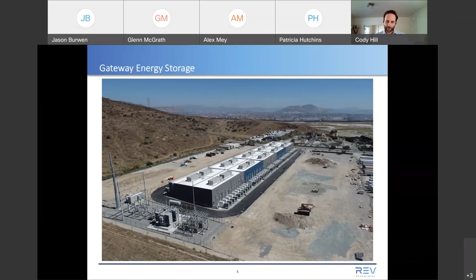These little gray boxes are the transformers that convert the 34.5 kV to low voltage for the inverters. The white boxes, each one is about a 3 megawatt inverter. It converts the AC to DC, and then the cables go inside to battery racks that look a lot like what you saw on the previous slide. Pretty much all of these battery storage facilities have that same architecture: 2 or 3 megawatt inverter stations is the most common, though you can also see smaller ones sometimes. It's really the same technology used on inverters from the PV space, so we've benefited from the scale of that much larger industry, being able to procure higher volume and lower cost, more mature hardware than we could back in the early days when I was doing this a decade ago.